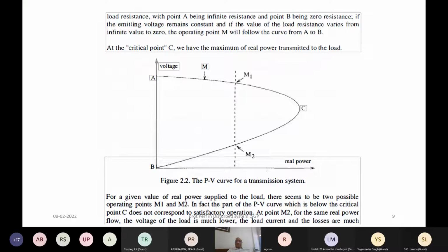This is the curve which we were talking about, where this is the sending end voltage, this is the receiving end voltage, and you can see as the line loading, this is the real active power loading, increases, there is a voltage drop, and the reactive power flow will increase, and beyond this point, voltage will collapse dramatically because of the behavior of the motive load again. Because the reactive power drawn is proportional to the square of the voltage.